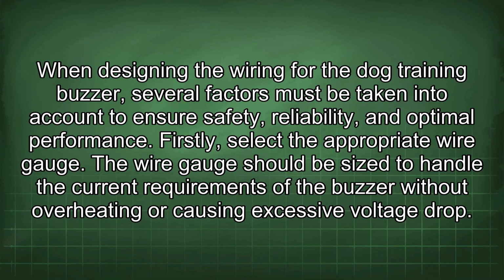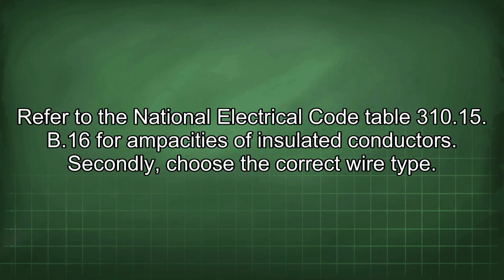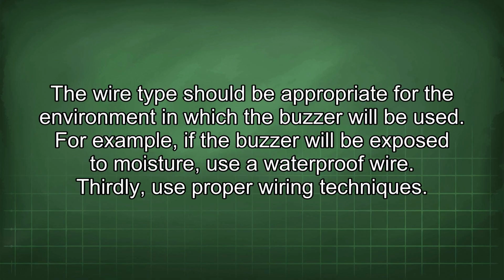The wire gauge should be sized to handle the current requirements of the buzzer without overheating or causing excessive voltage drop. Refer to the National Electrical Code Table 310.15(B)(16) for ampacities of insulated conductors. Secondly, choose the correct wire type. The wire type should be appropriate for the environment in which the buzzer will be used. For example, if the buzzer will be exposed to moisture, use a waterproof wire. Thirdly, use proper wiring techniques.